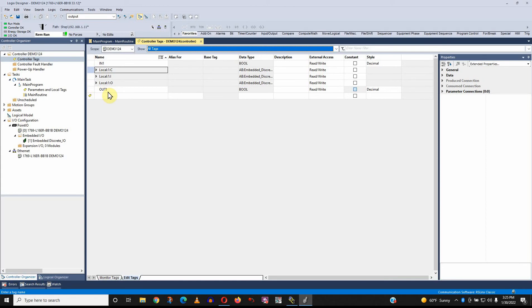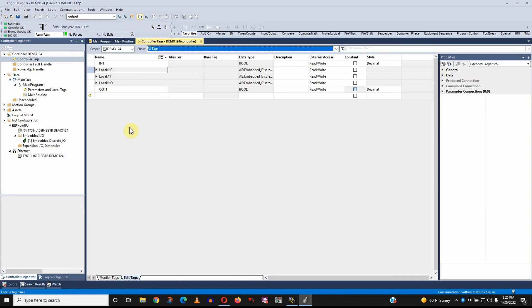So if you want to delete tags, let's say you've got lots of tags and you don't like all those extra unused tags floating around, you can filter for them and then delete them out. Even while it's running, you can do that. There's no real risk, there is a small risk. There's always a risk. Let's say I've created a tag and I'm using that tag as a place to import data into from another processor. If I delete it, the incoming data has nowhere to go. So I suppose there's always a risk.